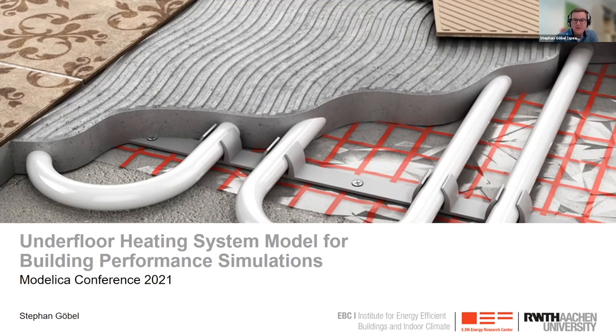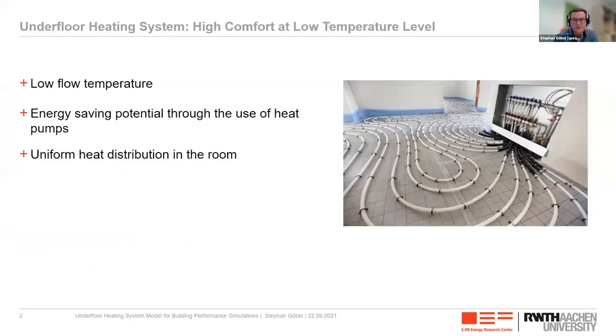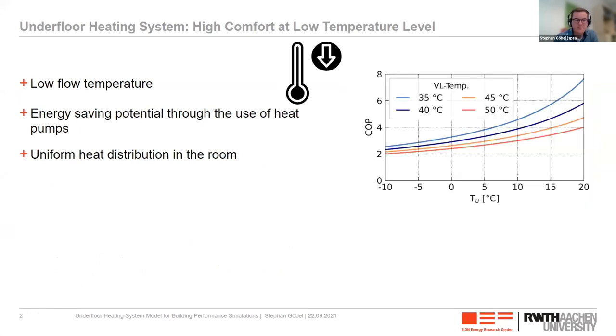To begin with, I will talk about the general properties of underfloor heating systems. First of all, it's the low flow temperature compared to radiator systems. This enables energy saving potential through the use of heat pumps. According to Carnot, the efficiency of heat pumps increases with decreasing flow temperatures.